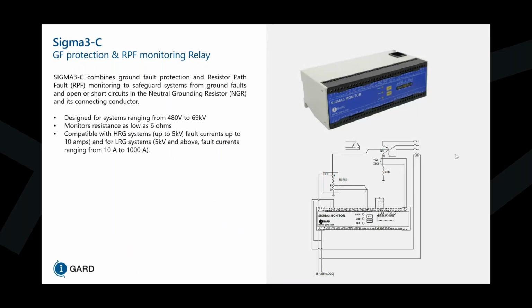So this is designed for systems ranging from 480 volts to 69 kV. It monitors resistance as low as 6 ohms and is compatible with HRG systems up to 5 kV and fault currents up to 10 amps, and for LRG systems, where if you're at 5 kV and above, and fault currents ranging from 10 amps to 1000 amps.